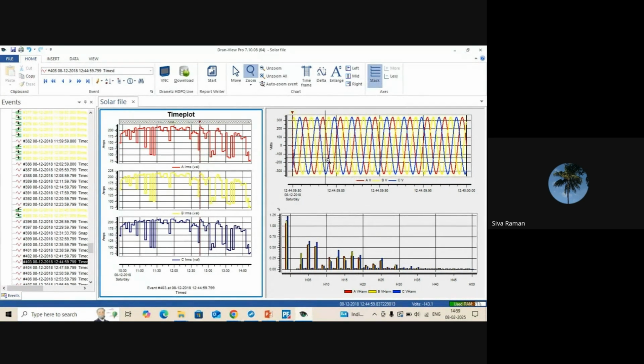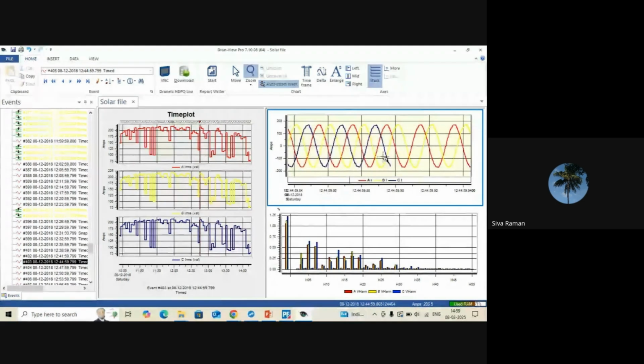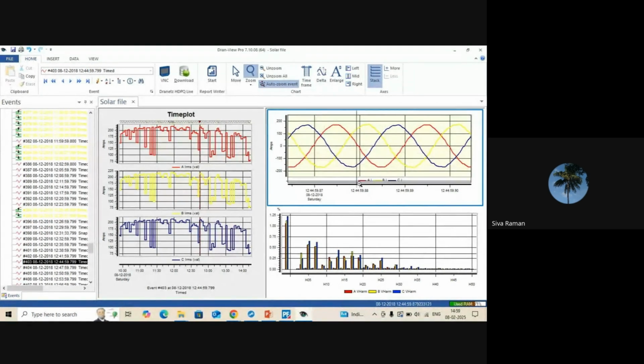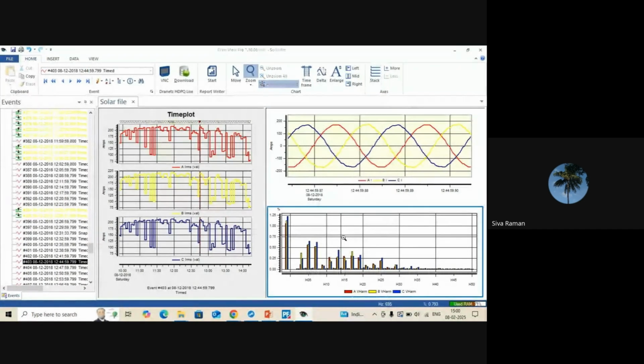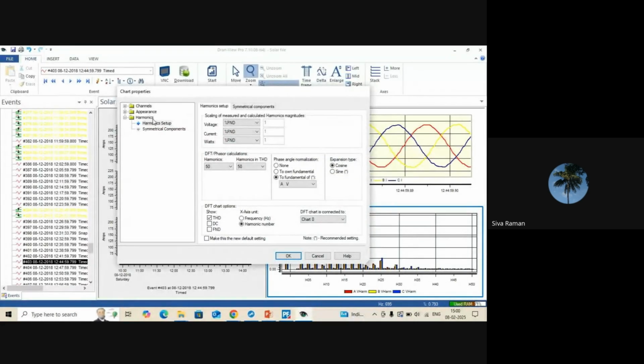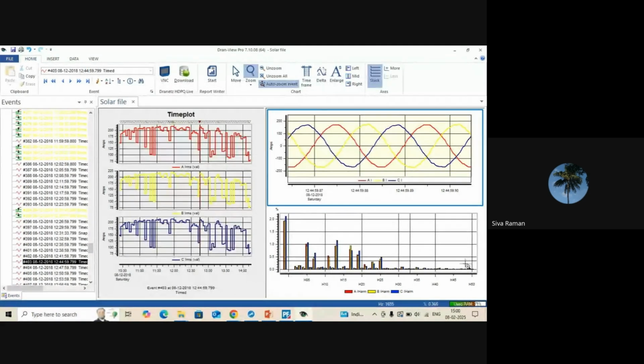I will set this side and select the current waveform. This is the current waveform. You can see there is a slight distortion in the current also. So I will plot here the current harmonic bar graph. In the current harmonics, THD is closer to 2%, almost 2%. The fifth order and 13th order are the maximum harmonic orders.